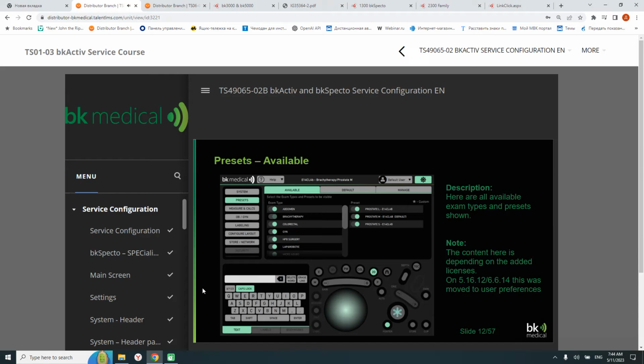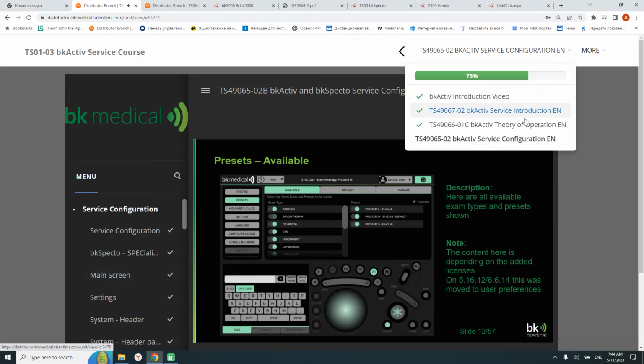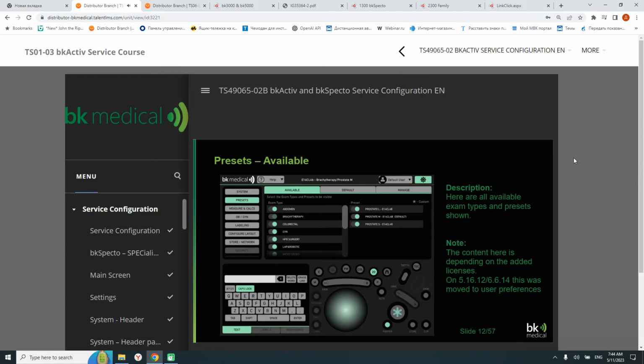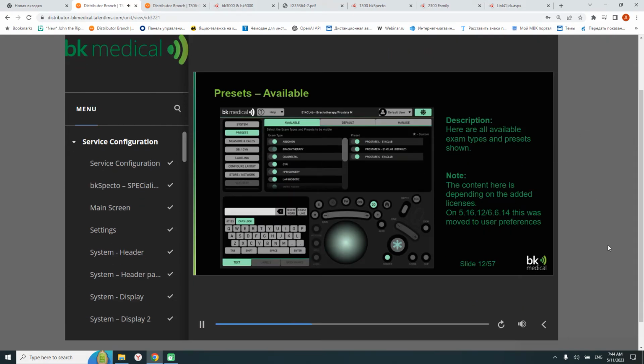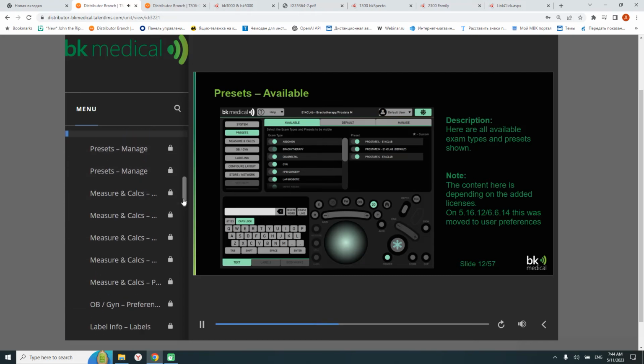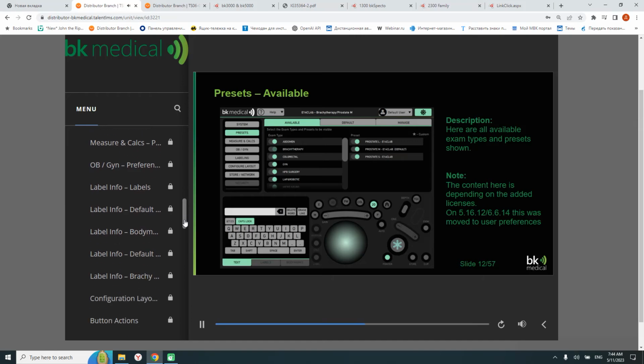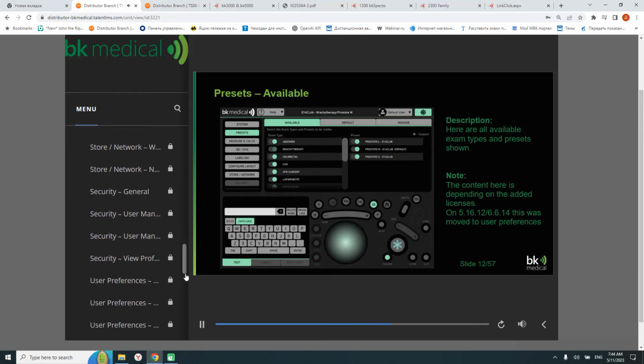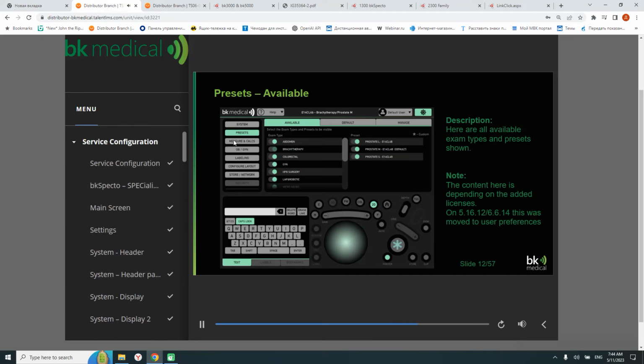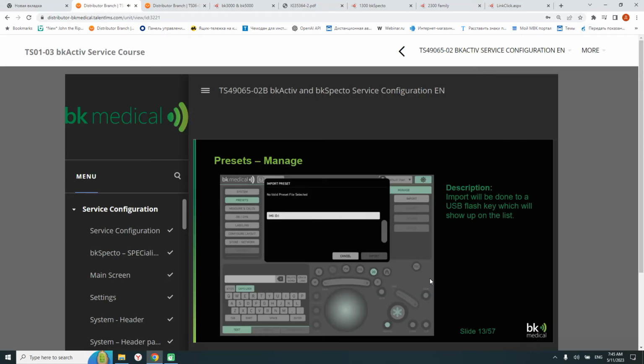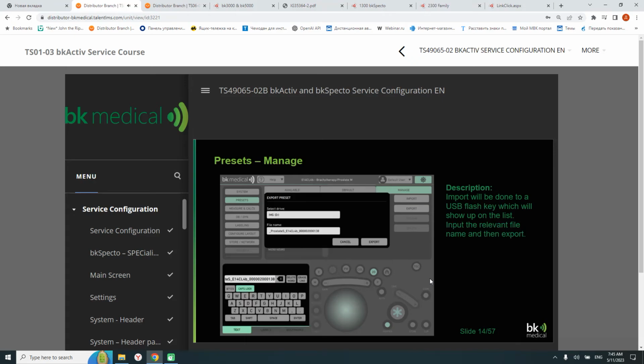The next category is presets. This is where the user can get an overview of all the available presets. The presets listed depend on the licenses submitted to the system. In the tab named Available, all exam types and presets are listed. Next to the exam type and presets, a green dot can be seen. This is where the exam type or preset is disabled or enabled. If an exam type or preset is disabled, it will not show up in the clinical workflow, and probes might not be possible to be used. To import, insert a USB flash key and select the drive and the file on the list. To export, insert the USB flash key, select it on the list, and name the file for export.